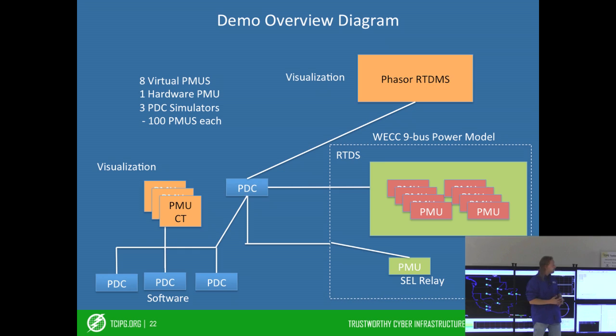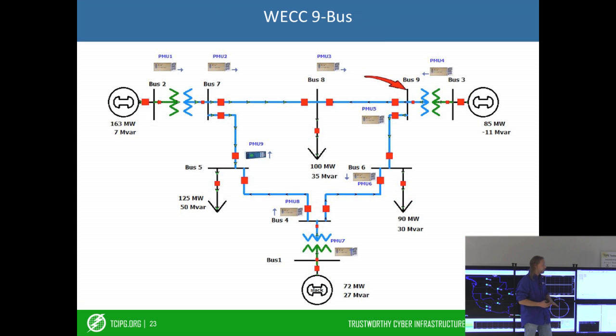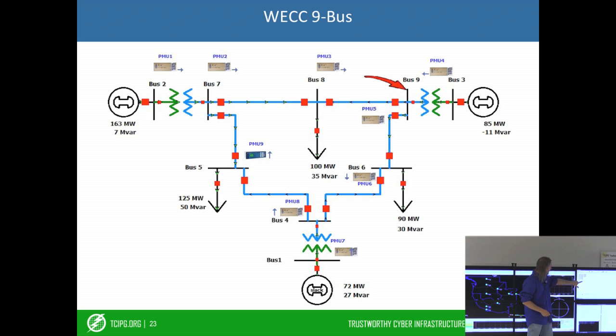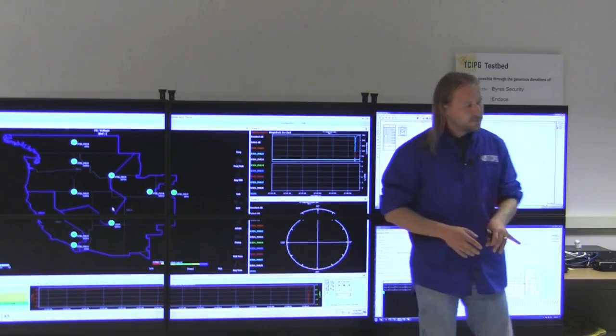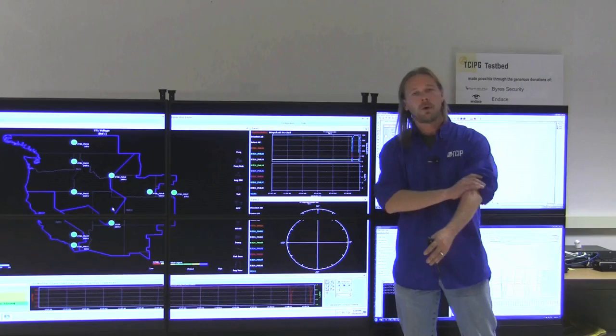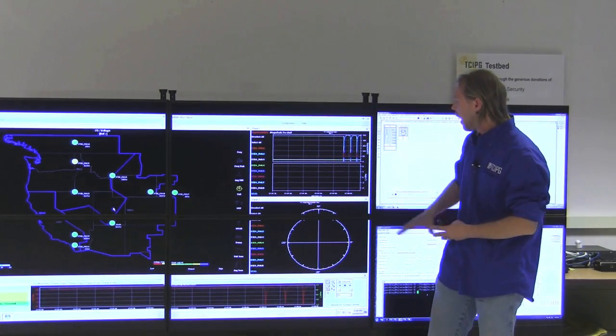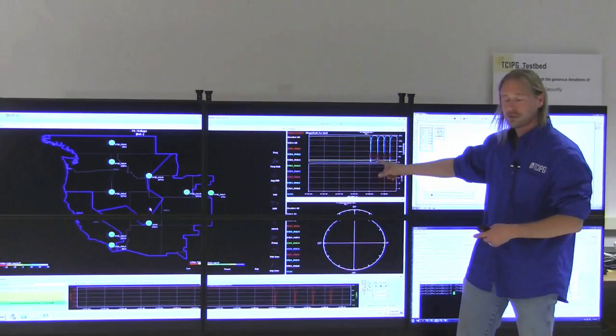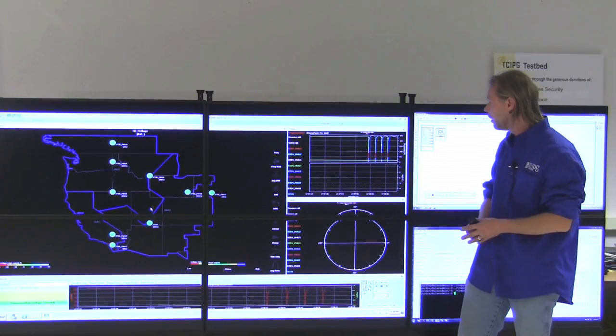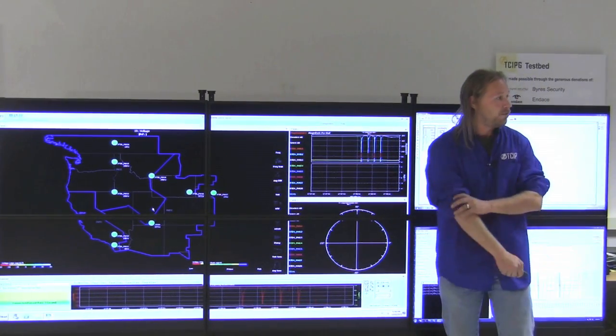We're going to introduce a short circuit fault on a WECC 9-bus model that's running on the RTDS. You can see that programmatically we've executed this fault. All of this data is flowing through the experimental network and then shows up here on Phasor RTDMS as a voltage drop that you see here, and then of course it returns back to steady state.